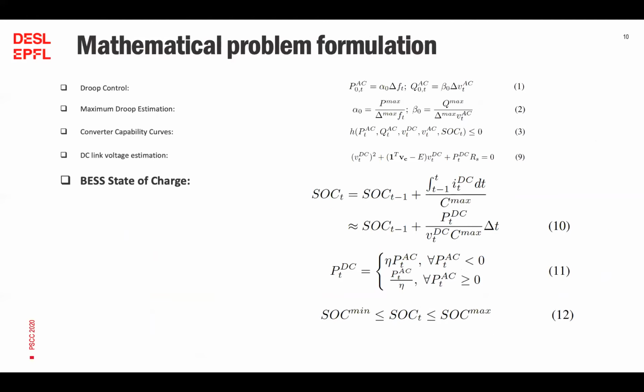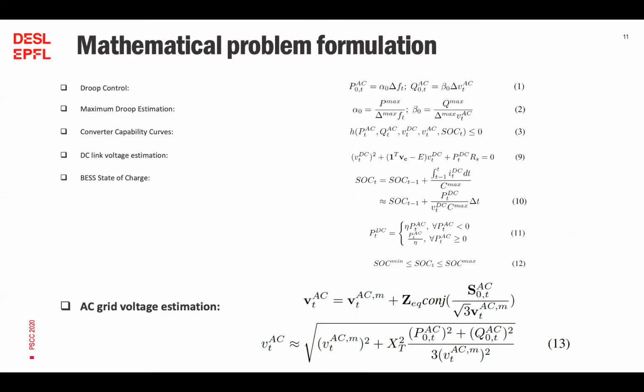As I said, the state of charge is of course extremely important as well, and this is obtained with the information of the state of charge at the previous time step and from the information of the DC power, which is in turn calculated thanks to the information of the initial AC power obtained with the alpha droop and the information of the efficiency. Finally, we also have the constraint that imposes a minimum and maximum limit of the state of charge during the period of the control session. Last but not least, we also need the information of the AC voltage to estimate the converter capability curve. And this is achieved via the Thevenin equivalent circuit model, as expressed by the constraint on the slide.